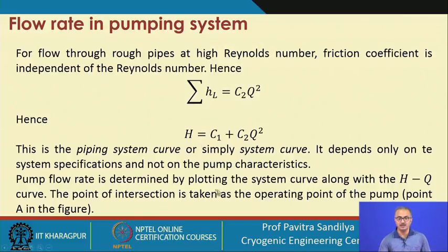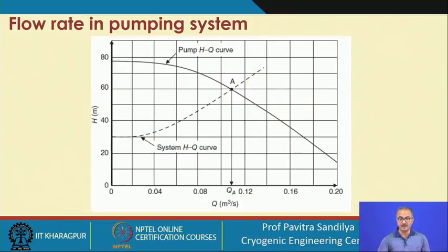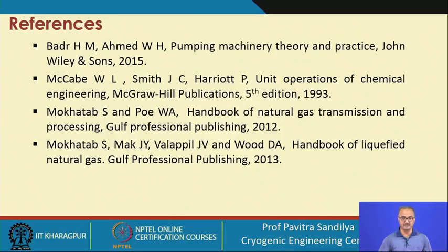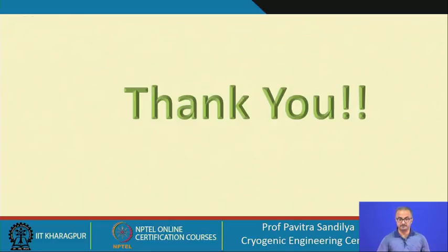To find the flow rate, we first plot the H-Q system curve (generated from the energy balance) and overlay the pump H-Q characteristic curve provided by the manufacturer. The point of intersection of these two curves is the operating point of the pump — the flow rate at which the pump should operate. This is how we determine the flow rate in a pumping system. These are the various books you can refer to for more detail about pump characteristics and the other topics covered. Thank you.